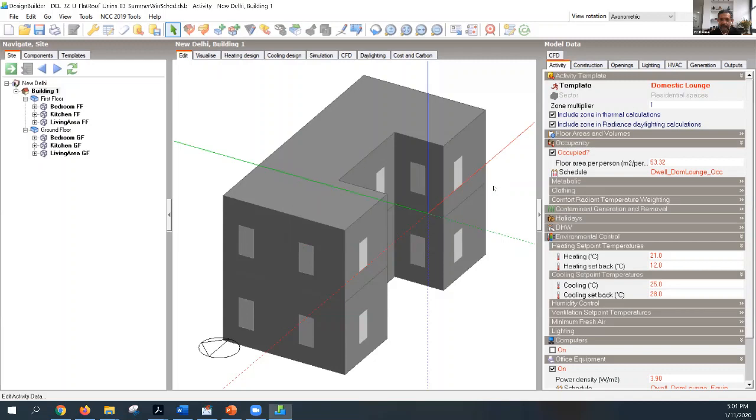Now, this is not a hard and fast rule. It's just something that we have decided in Australia as consulting practice. And it's got a bit of history. You know, a typical ceiling tile is 1.2 meters deep. And so the engineer said, okay, 3 ceiling tiles. Okay. There is research in the world that says that somewhere between 3 and 6 meters is what a perimeter zone should be.